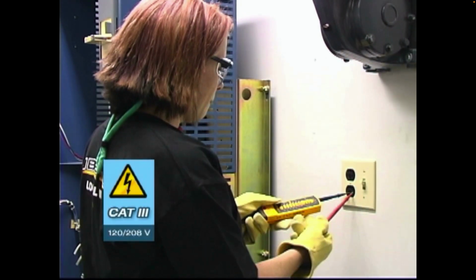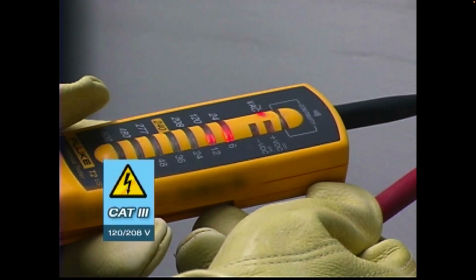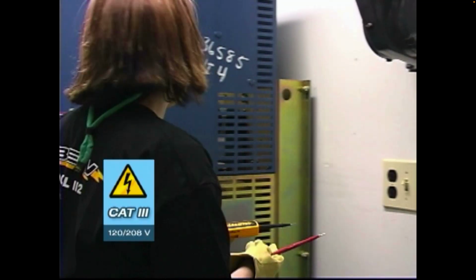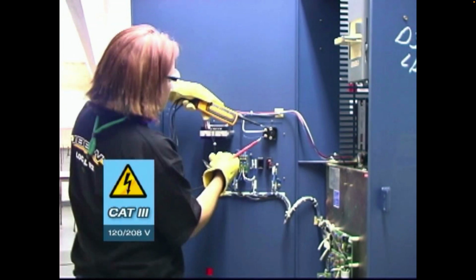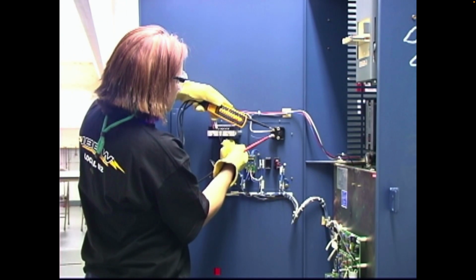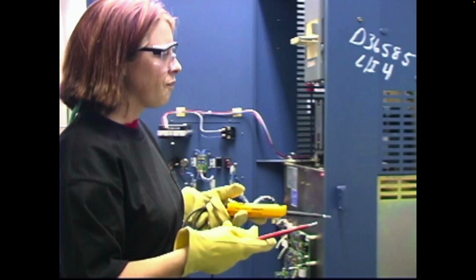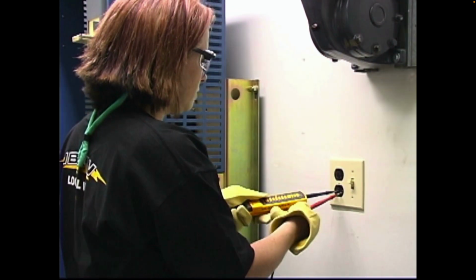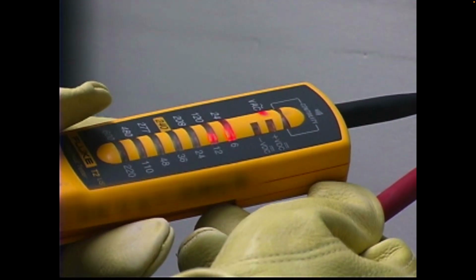To make sure your meter is working, use the three-step test method. First, test a circuit you know is live. Next, measure the target circuit. But before you conclude that circuit 2 is dead, retest the known live circuit. This way, you know your meter is working.